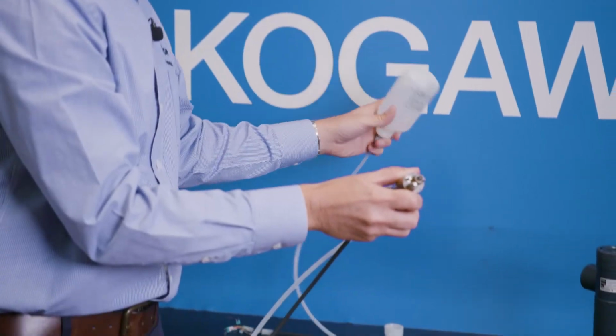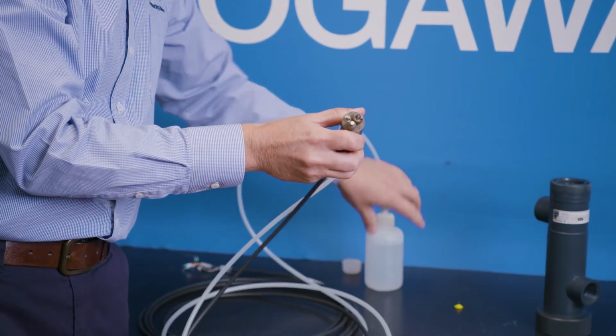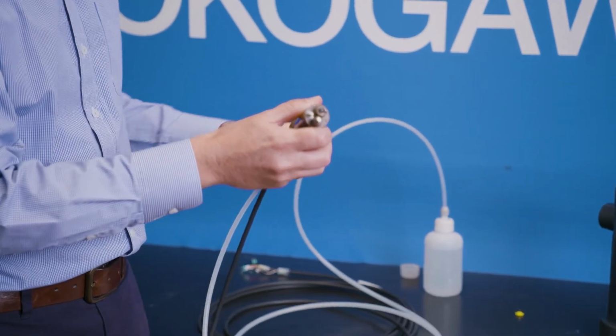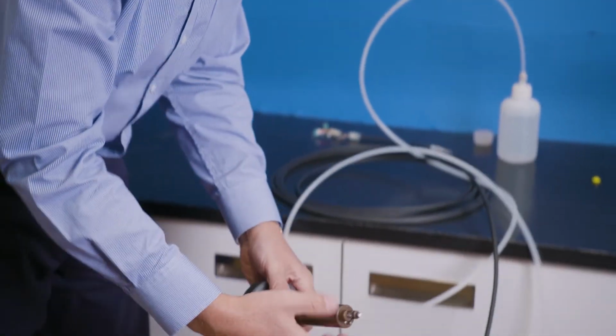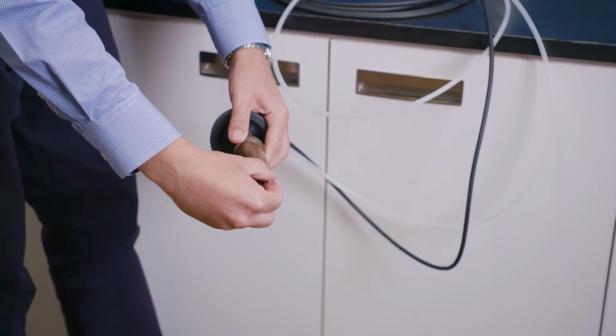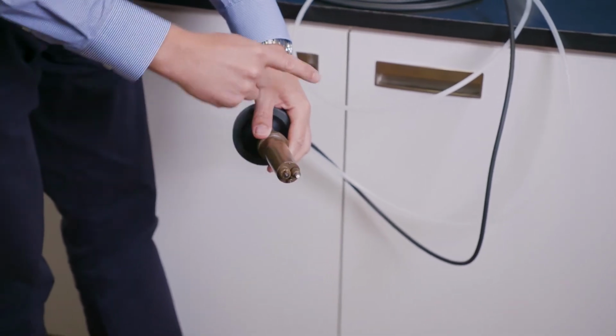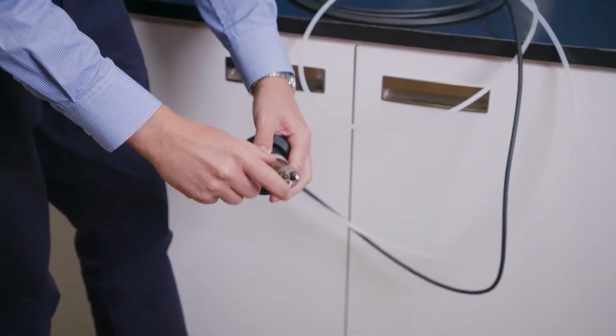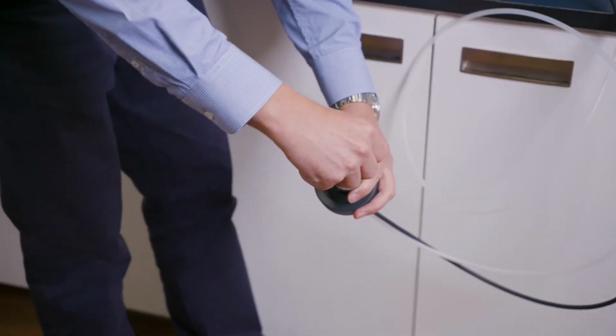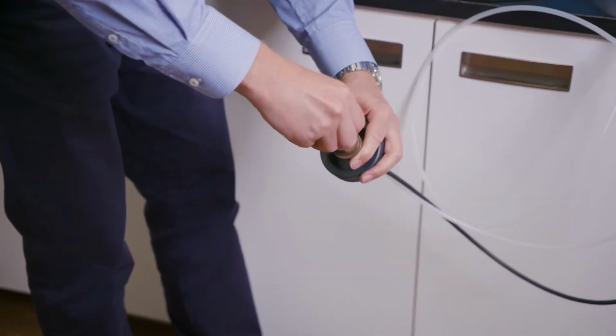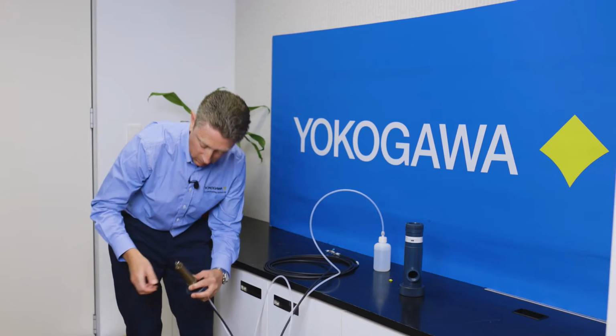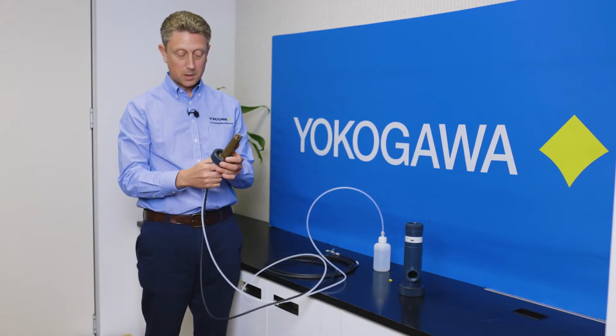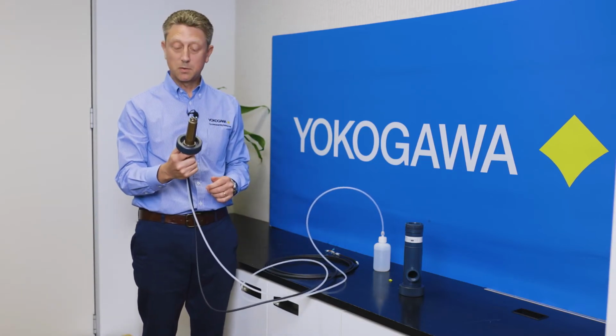And with our pH probe now at a position that is lower than the KCL bottle, out of that reference junction we can bleed a little bit of that KCL solution through. Once it comes through, we know that it's full and we can screw the reference junction finger tight into place, and the sensor is ready to be used for measurement.